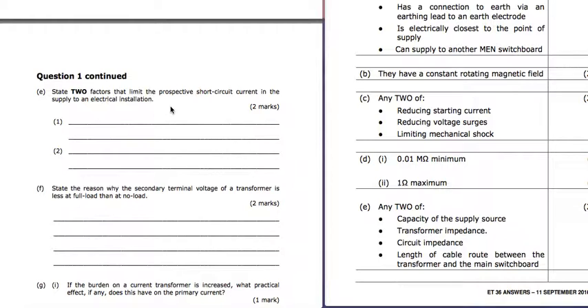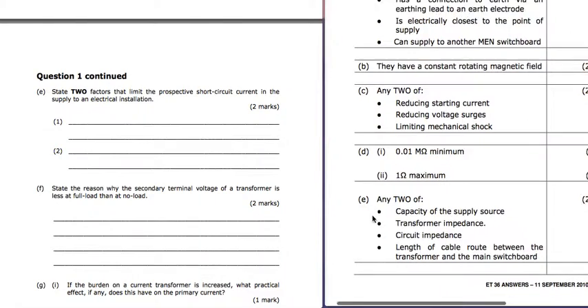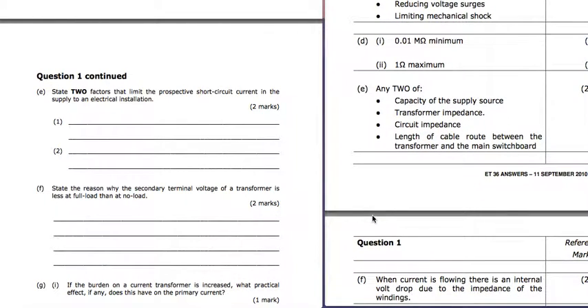Two factors that limit the prospective short circuit current in a supply. So what's the maximum short circuit current we can get? Well, it's going to be dependent on the capacity of the supply source. So the power, the MVA of the supply, how much it can push out. The impedance of the transformer, because the current is going to be voltage over impedance, over Z. The circuit impedance, so both of those impedances, and the length of the cable between the transformer and the main switchboard is going to limit the current.